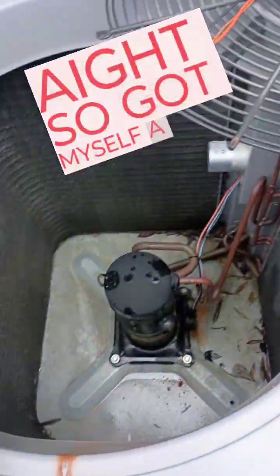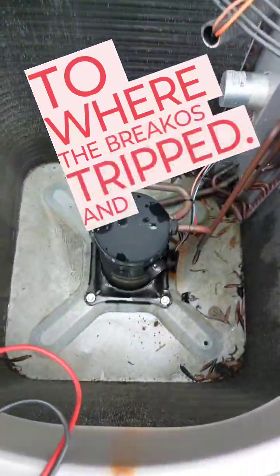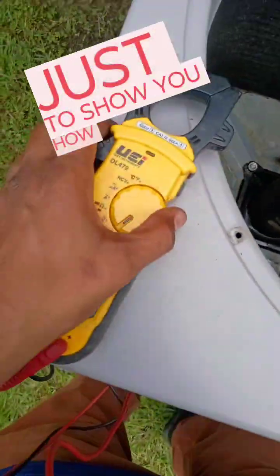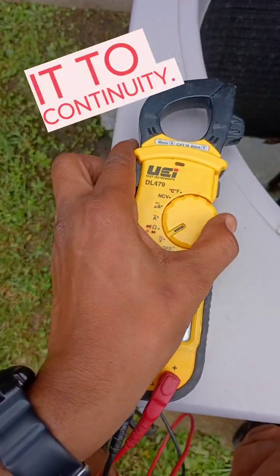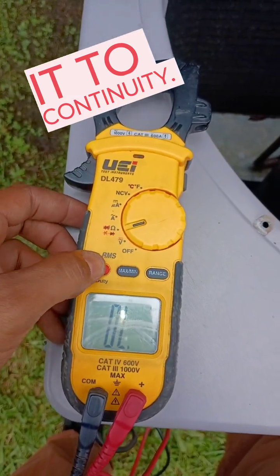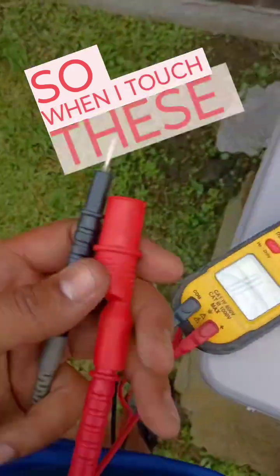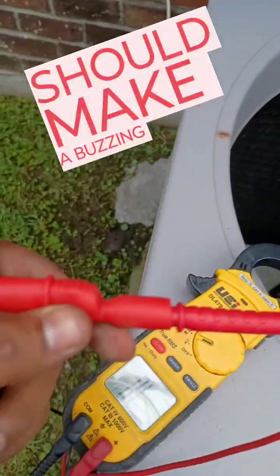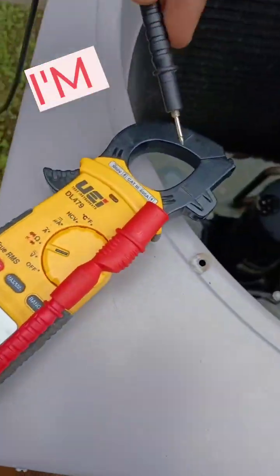The breaker was tripped, and I'm going to show you how to test the compressor. We're gonna switch it to continuity mode. When I touch these two leads together, it should make a buzzing sound — bear with me, I'm using one hand.